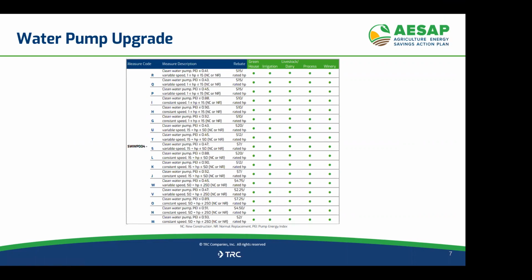Okay, cool, very cool. A PEI of 1 is a standard pump based on DOE regulations. For these incentive calculations, they assume that a standard pump, or what's typically purchased, is approximately 0.94 or 0.95. So the savings is relative to that. That's why if you get a 0.93 PEI pump, it has a relatively small incentive compared to a 0.88, because that's relative to a baseline assumption of 0.94 or 0.95, depending on the size of the pump.